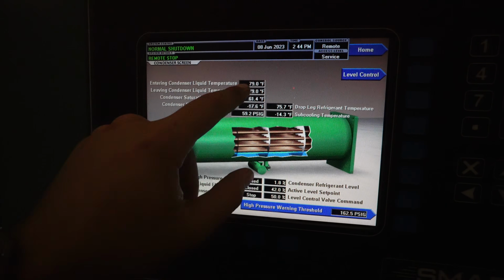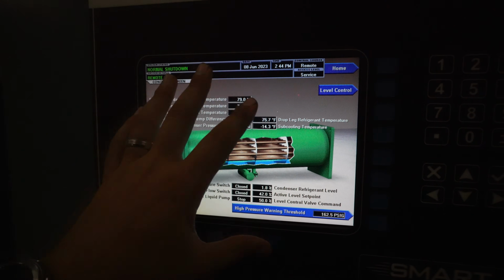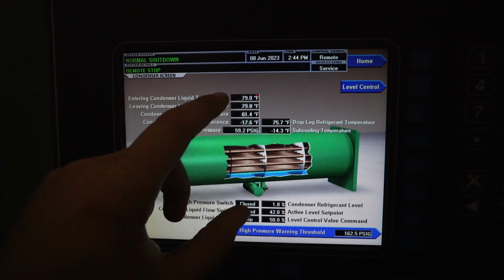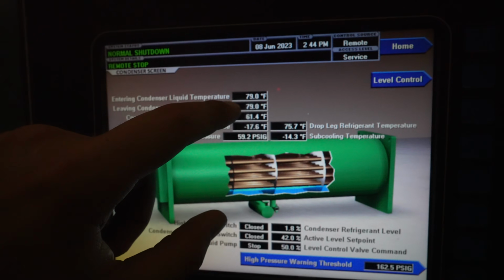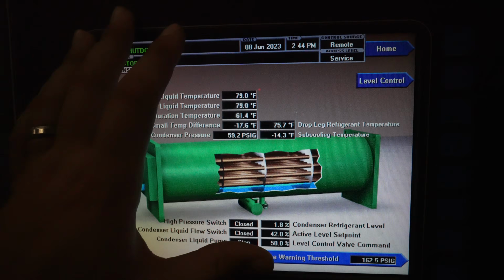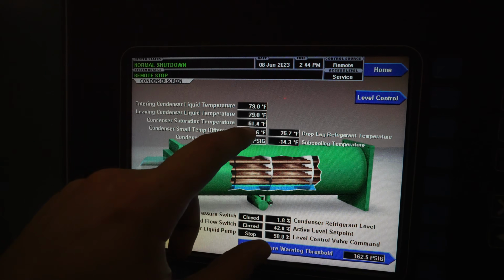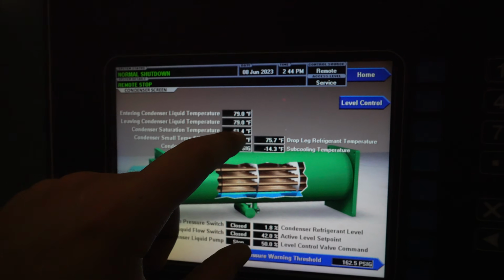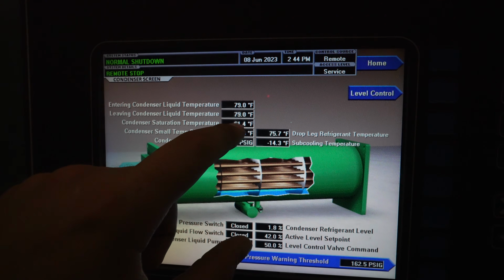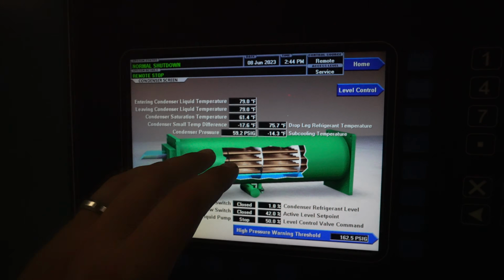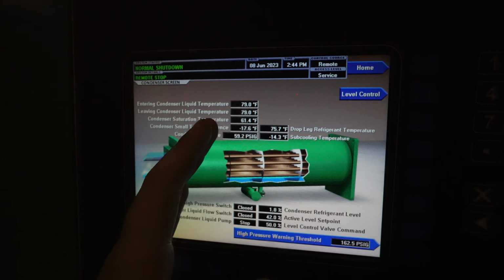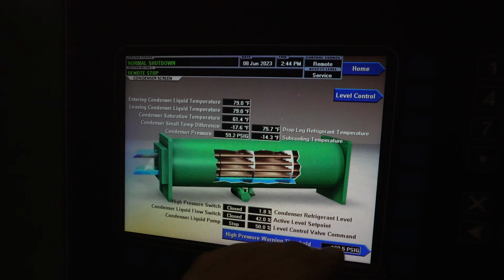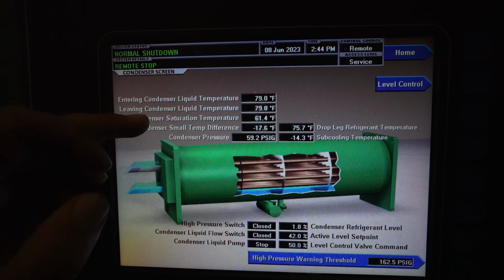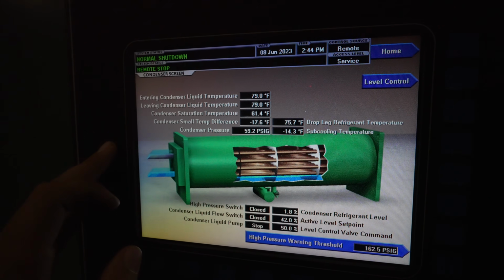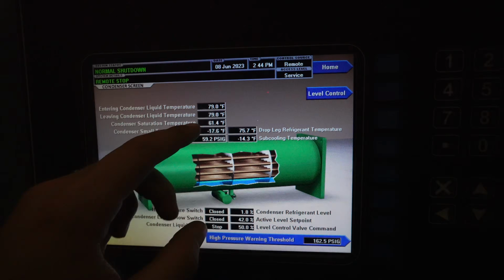And that's where I saw that we had really high conditions here on the condenser, and it was a little lower. So when I first walked up to it, we were sitting about 87, so we were pushing that 10, 11 degrees split across the condenser, but we were still running about a 91 to 92 on the condenser saturation. So by me adjusting that liquid level, I increased that by a couple of degrees on both sides, the saturation and the leaving water temperature, which is what made me begin to realize I possibly had a flow issue.